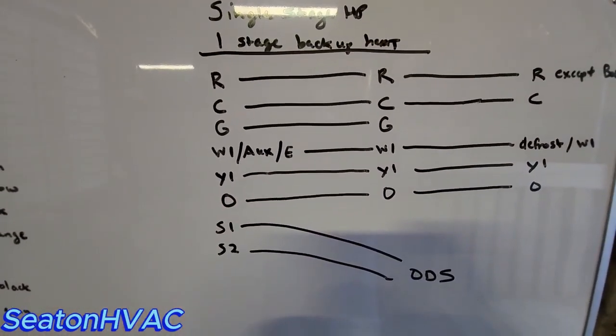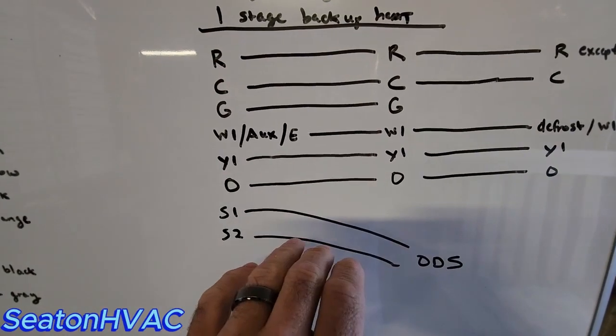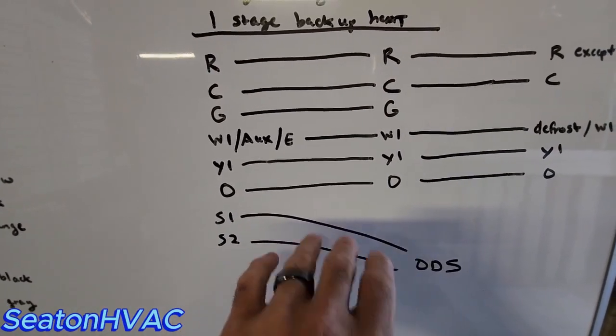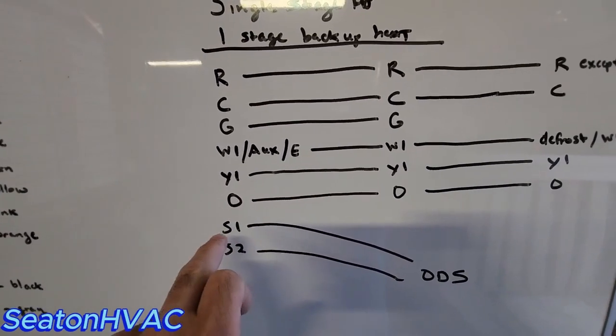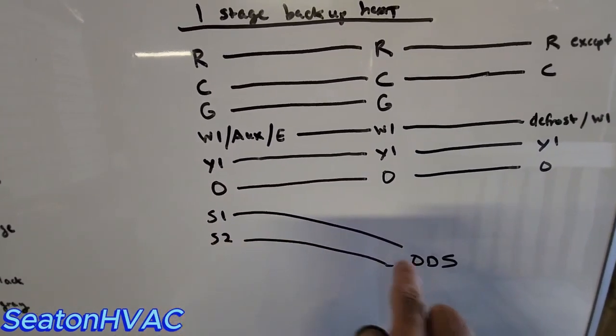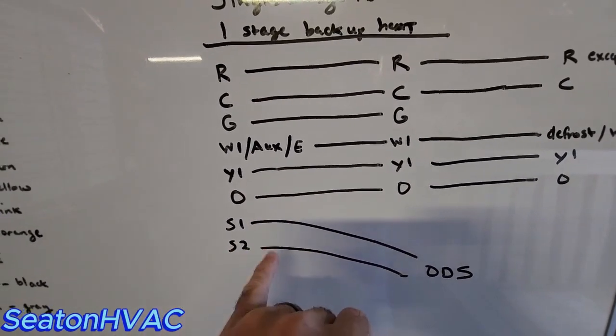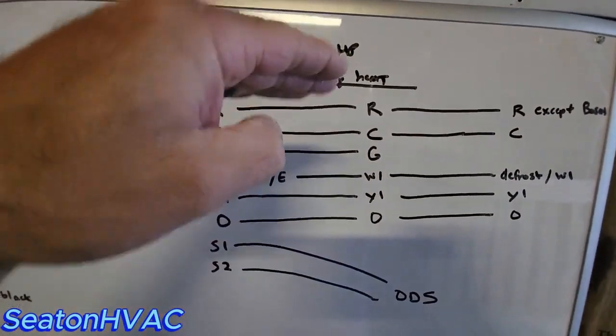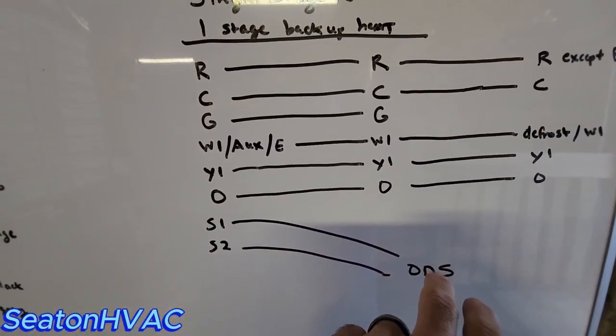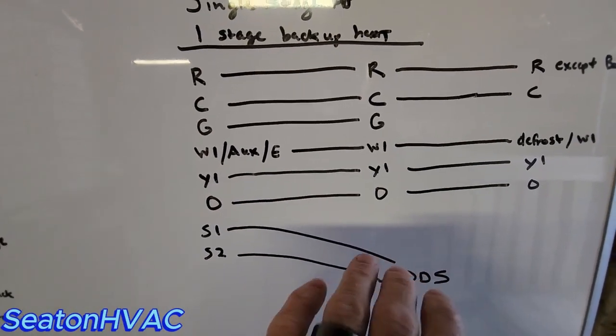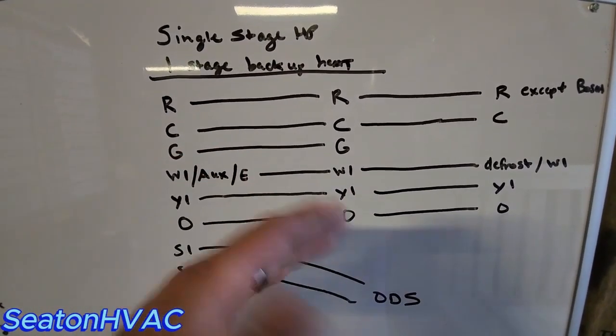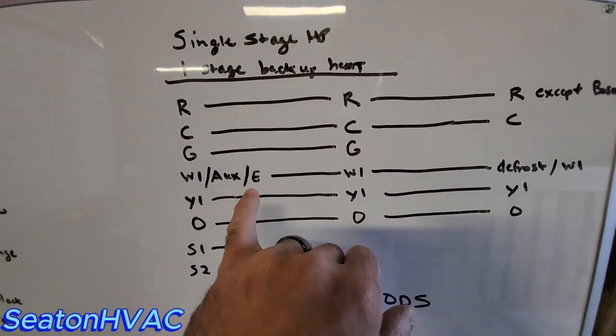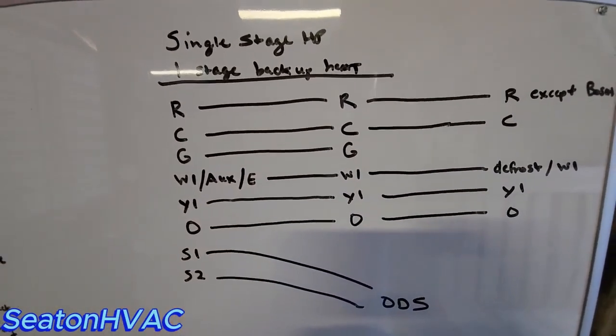Some of the Wi-Fi thermostats are doing it via the closest weather station, so it'll get the weather data that way. I think this is the best way to do it. Find a suitable place on the house to put your outdoor sensor. It's just a 2-wire sensor. Again, I use black and gray for those. This is assuming a 10-wire thermostat wire, okay? And then, find a shaded place to put that. You'll get the best data, and it'll lock. That's used to lock out your backup heat. So let's say you only want the heat pump to run down to like freezing, and then you would have your auxiliary heat kick on below that temperature, okay?